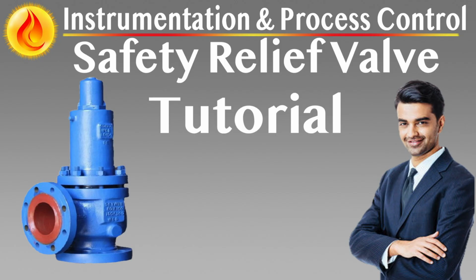Special design scenarios. Pilot-operated relief valves are particularly advantageous in systems with large inlet pressure drops, i.e. greater than 3% of set pressure, as pilot placement compensates for signal loss. High-pressure gas compressors, where discharge lines experience large pressure swings and capacity demands. Critical relief systems, where standard spring-loaded valves may not reseat accurately or may experience chatter.